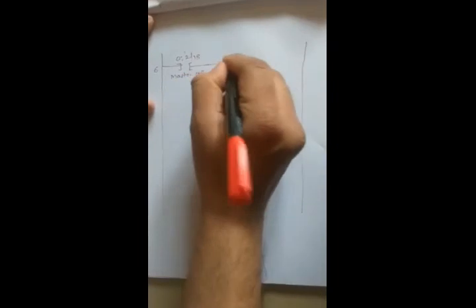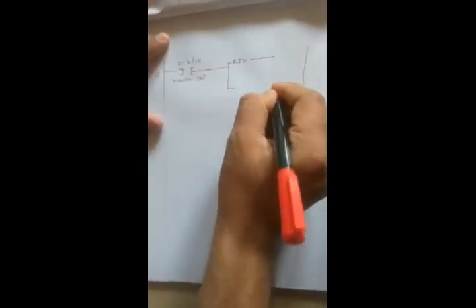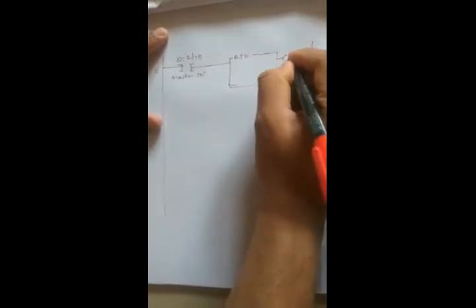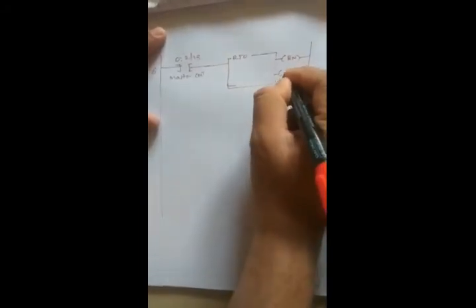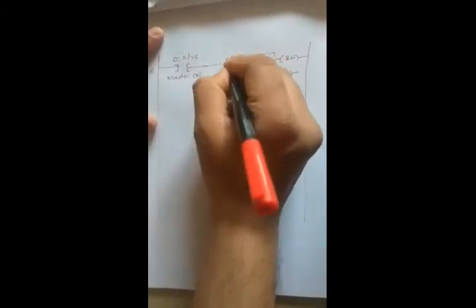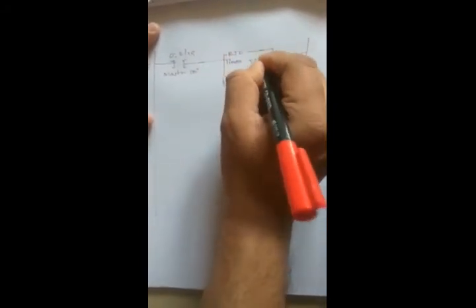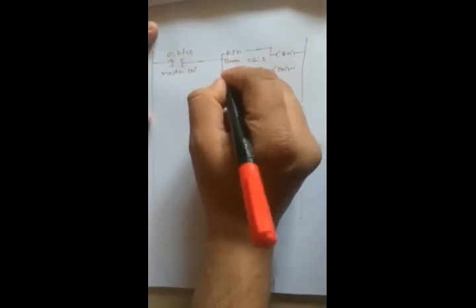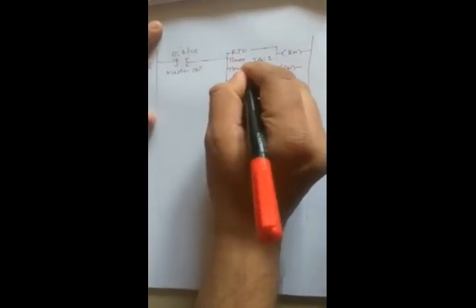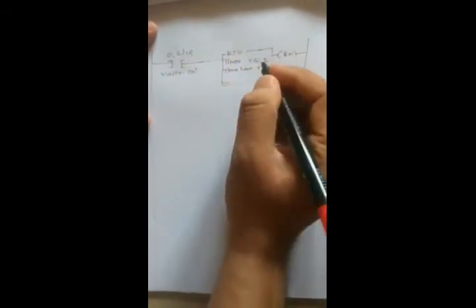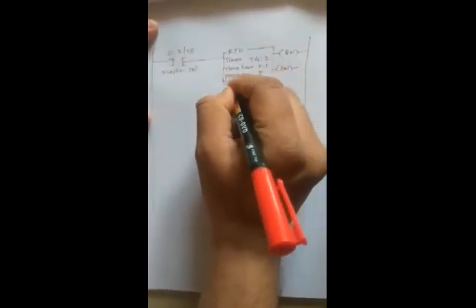And again you have to use one retentive timer for outputs 4 and 5. So write down enable and done bits respectively. Then the timer we have to use over here, we already mentioned in the list of inputs and outputs. Then the time base required will be 0.1, and the preset value for this timer will be 5. Then the accumulator will definitely start from 0.